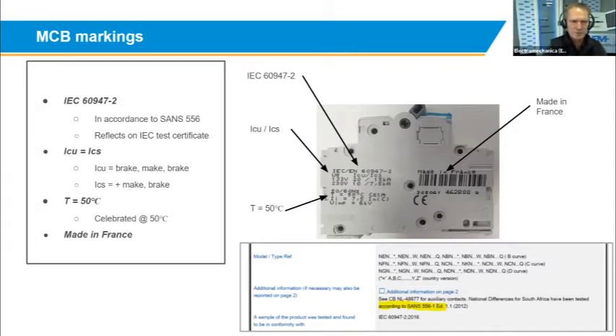Then also important for the South African market, because we are a fairly warm country, the circuit breakers have been calibrated to 50 degrees C. So when it's installed in a distribution board, the temperature inside there can go up to 50 degrees, and you do not need to derate your product.